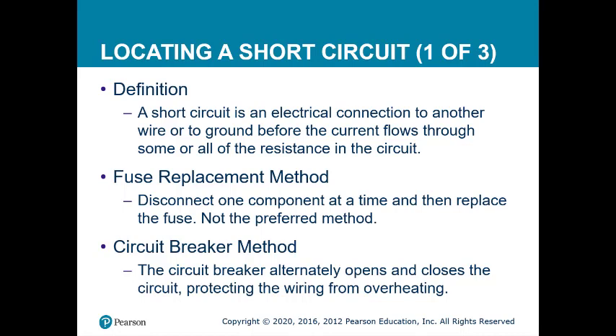The definition of a short circuit is when an electrical connection on the power side comes in contact with a component on the ground side, completely skipping the load. When it skips the load, it skips the engineered resistance for the circuit, causing an increase for the current threshold in that circuit, which then causes the fuse to blow. There's many ways of trying to find a short circuit.